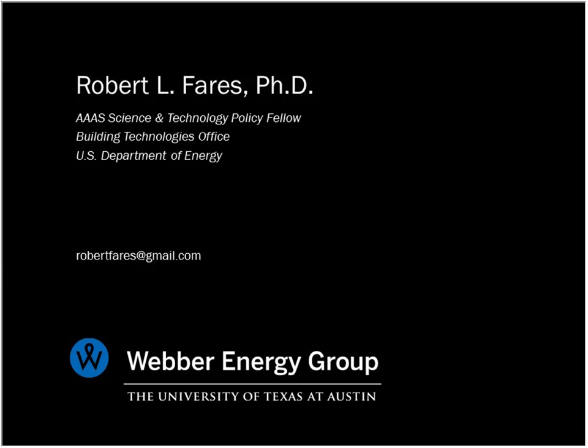And so I'd say there are a lot more cases where solar plus storage is going to be economically viable for commercial customers because of this demand charge issue. Because if you're adding solar and say it tends to peak at about 2 p.m., but your building is still drawing its peak amount of power at around 5 or 6 as people are starting to leave work, then that solar is not going to do a lot to reduce your peak demand. But if you add some storage and you can shift that solar production to another time of day, you can really significantly reduce your demand charges.